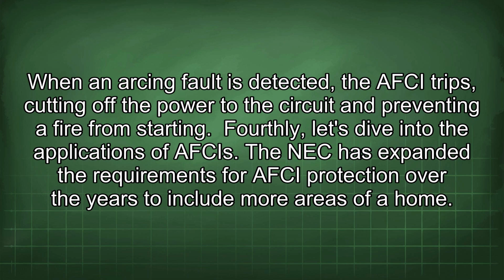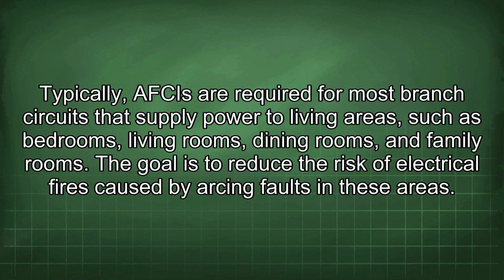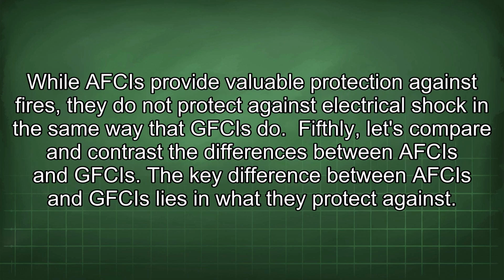Fourthly, let's dive into the applications of AFCIs. The NEC has expanded the requirements for AFCI protection over the years to include more areas of a home. Typically, AFCIs are required for most branch circuits that supply power to living areas such as bedrooms, living rooms, dining rooms, and family rooms. The goal is to reduce the risk of electrical fires caused by arcing faults in these areas. While AFCIs provide valuable protection against fires, they do not protect against electrical shock in the same way that GFCIs do.